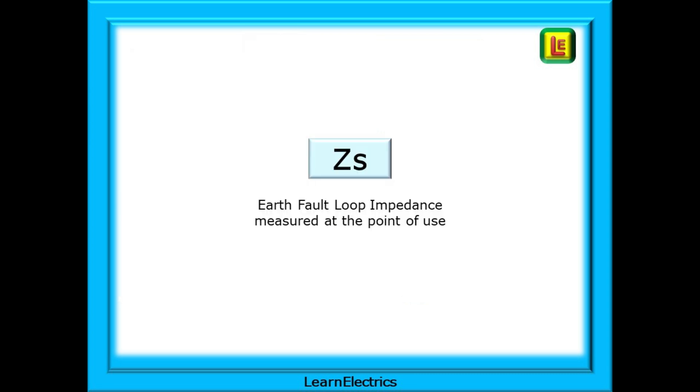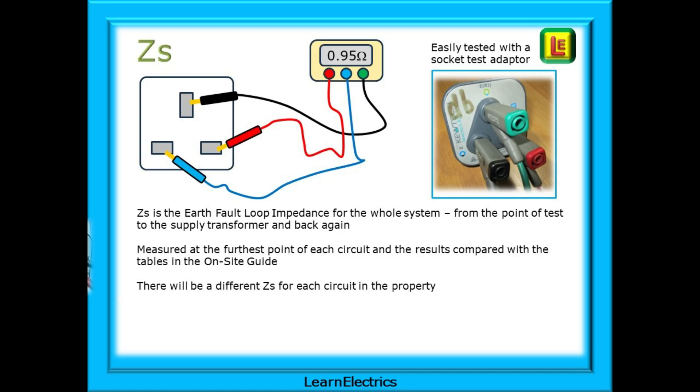Let's not forget ZS, the earth fault loop impedance measured at the various points of use around the property. ZS is the earth fault loop impedance for the whole system from the point of test to the supply transformer and back again. It is measured at the furthest point of each circuit and the results compared with the tables in the on-site guide. There are various test adapters that allow us to carry out ZS testing without dismantling the circuit. Shown here is a very useful socket test adapter. They are also available for lighting and other uses. There will be a different ZS for each circuit in the property and we have videos that cover ZS testing in great detail.